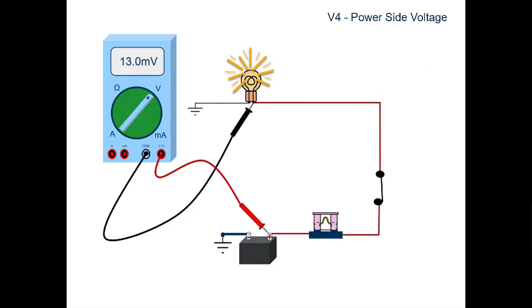If we were to open the switch on the power side, we should expect to see full voltage on the meter. With the switch closed, if the fuse were blown, the meter would also show full voltage. As in the example with V3, if we were to have an open on the ground side and an open on the power side, we would see ghost voltage on the meter.